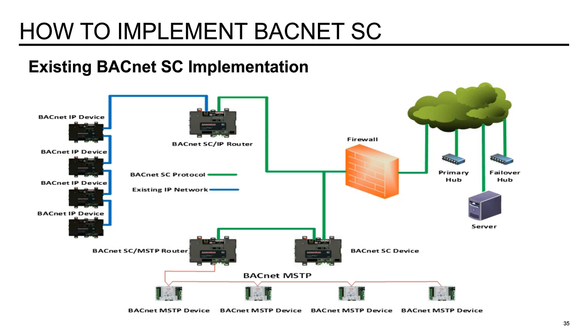Justin, you want to add anything to that? Yeah, that's what I would say. Ring is, I think, a layer 2 protocol. BACnet SC is an application layer, so it would run on any ring type protocol. The ring is managed through the switch, which closes and opens the switch ports. So I don't see any issue with running BACnet SC on a ring protocol.